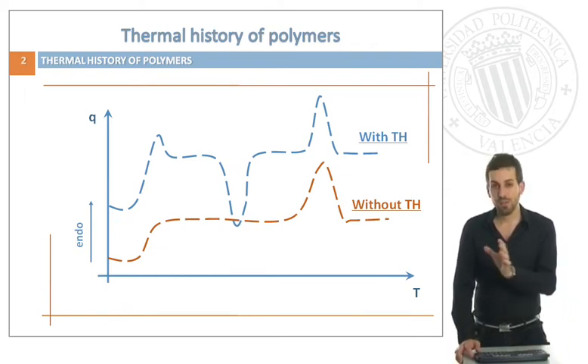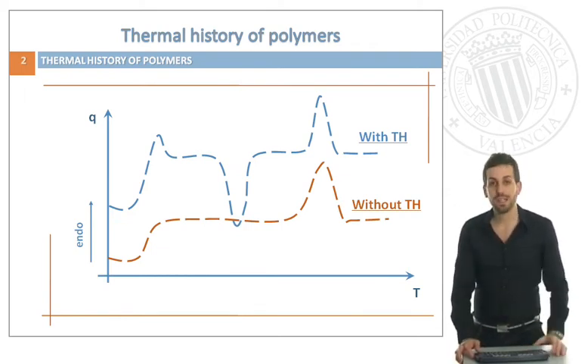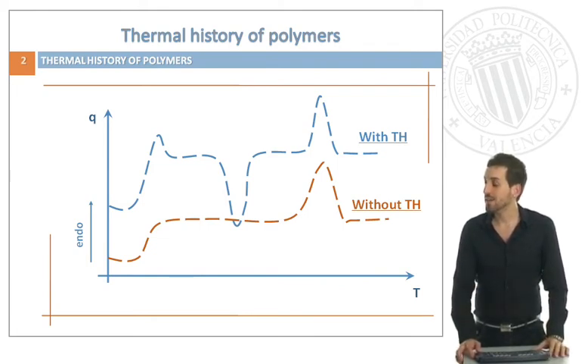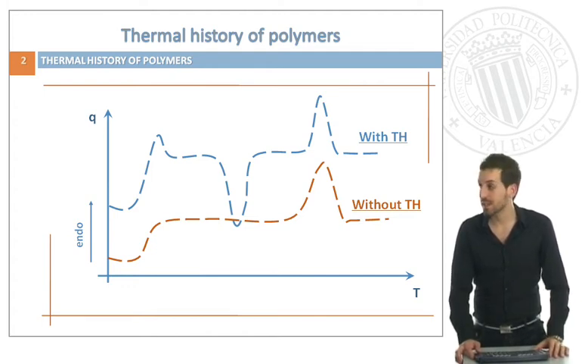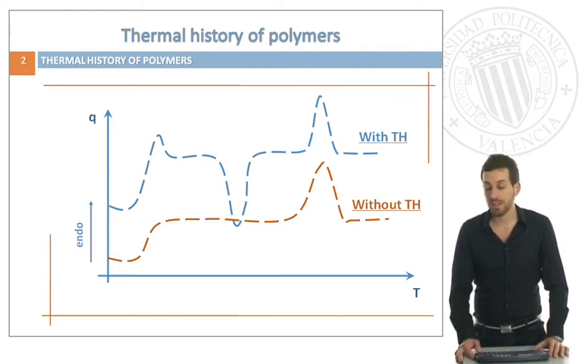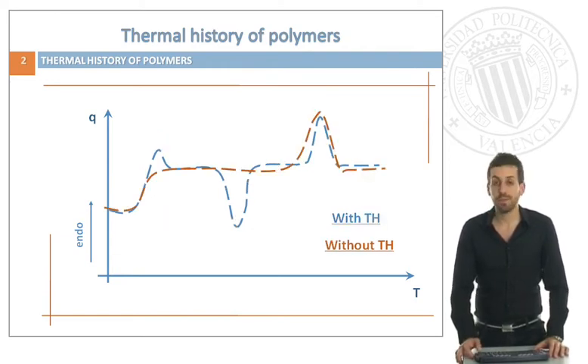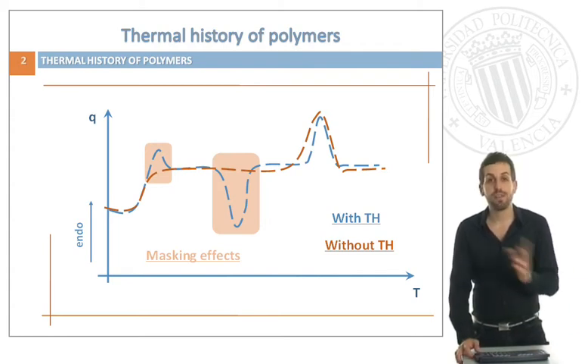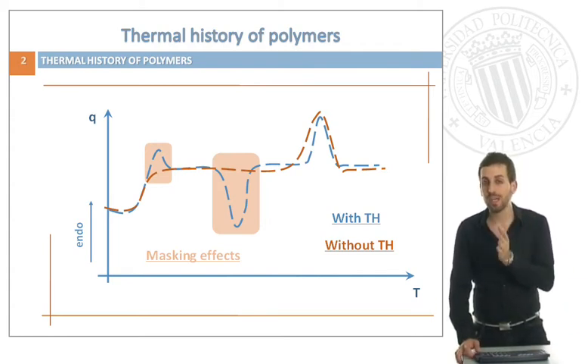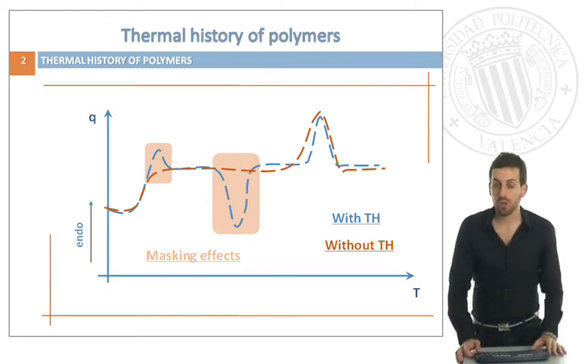Let's have a look at one example. In the blue scan we can see the response of a DSC of a polymer with thermal history, and the red one is without thermal history. If we superimpose them we can see these masking effects, so we have to know if we are really interested in them or not.